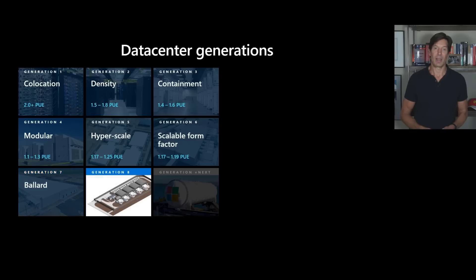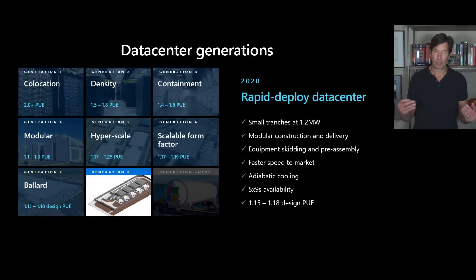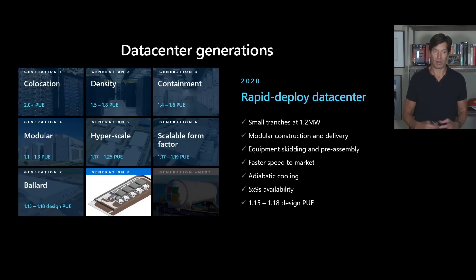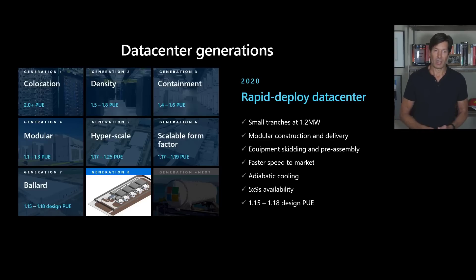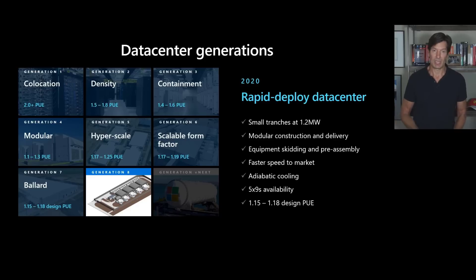We've taken the Ballard design further with a rapid deployment version using modular pre-construction, which can be set up very quickly at smaller footprints than the full Ballard minimum. This allows us to deploy new regions extremely rapidly, as a trade-off of slightly higher initial cost for speed of deployment. Once we initially land, as demand grows we can build full Ballard data centers on site to continue expanding. Based on the Ballard design, these achieve PUEs of 1.15 to 1.18, and you can see how successive generations have driven our PUE down over time.